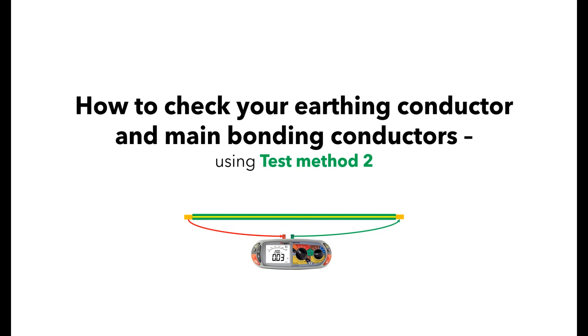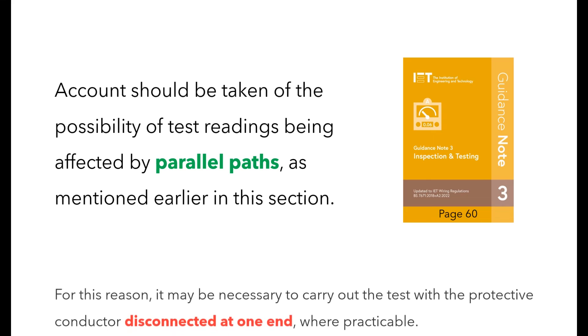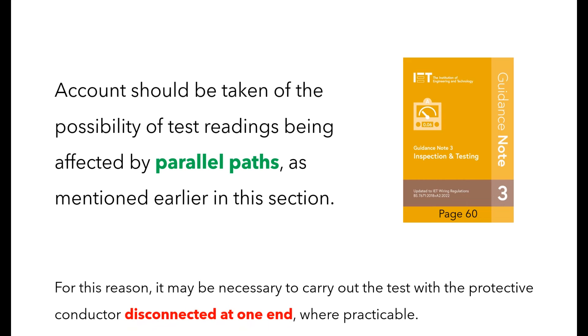In this video we are going to check our earthing conductor and main bonding conductors using test method 2, which is often referred to as the long lead method as you may need an extension to your test leads like this one. In the newest edition of GN3, page 60 talks about the possibility of test readings being affected by something we call parallel paths, which we will talk about shortly. The thing I want you to draw your attention to is highlighted in red, and that is you will have to disconnect one end of your conductor to remove the parallel paths.